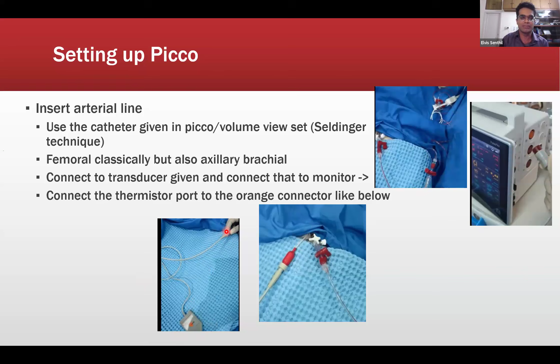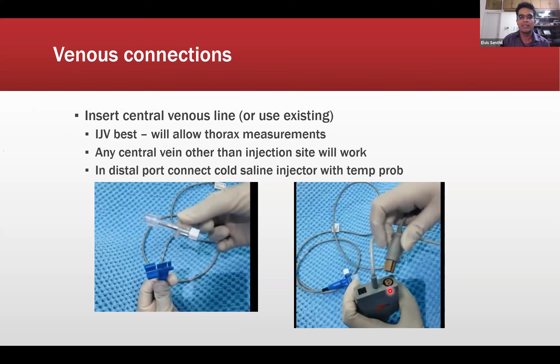Next thing you want to do is there's an extra line and you want to connect it to this cable, which is coming from this large port with an orange marking on top. This is the thermistor which measures the temperature. For the venous side, you have a plastic injection port, and this has a blue connector which you attach to the plastic injection port, and the other end of the blue thermistor is connected to the orange device as such.